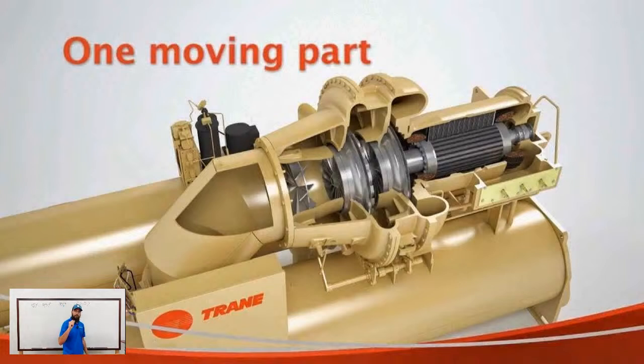A visual representation of that is, if you're looking at that diagram, you see the impellers, which we talked about yesterday, in the middle of that compressor. Right to the left of those impellers, where the suction elbow ties in, you'll see these little blade-looking things sitting in there. That is your IGV assembly. Those are literal paddles, and they'll be in a triangular shape fashion. How they're exactly designed depends on the manufacturer.